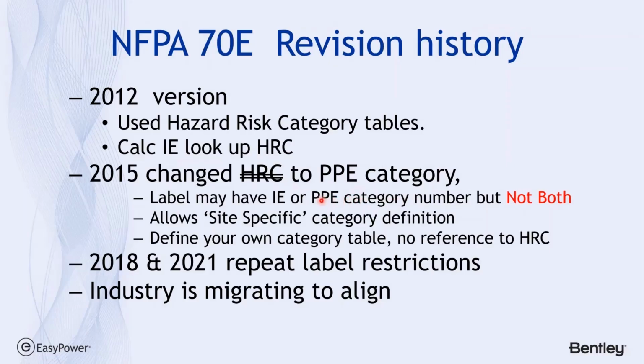Now, it's all well and good that someone comes and says, nope, it's my plant, I want my labels this way, and my safety manual is based upon the HRC reference, and so I don't want to change all my manuals. My people are being trained to utilize the HRC category. Again, it's a consensus standard, and so this allows me to define my own category table and just define the incident energy and the PPE rating without referring to the HRC. So this is a workaround that's relatively simple, but you're going to have to define your own category table and, again, not refer to the old-fashioned HRC.